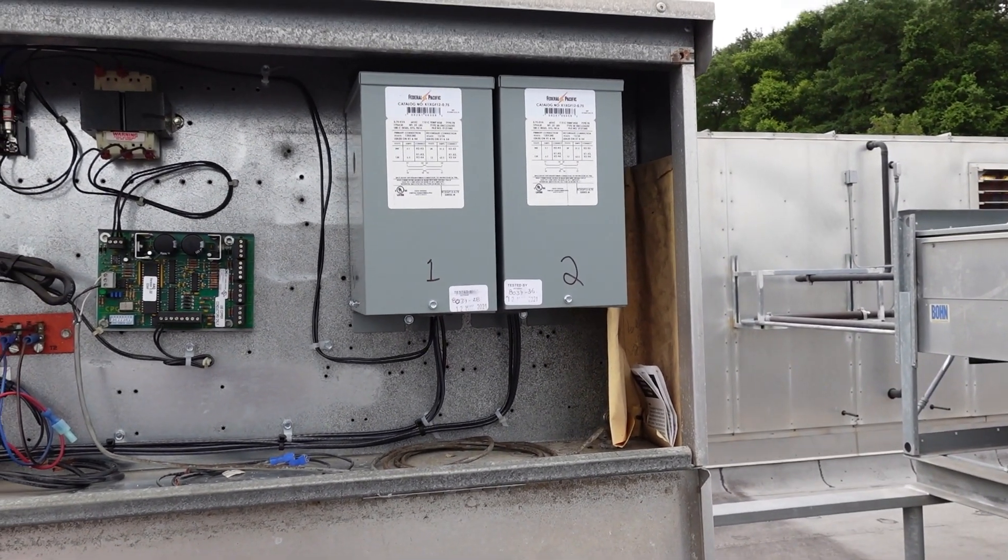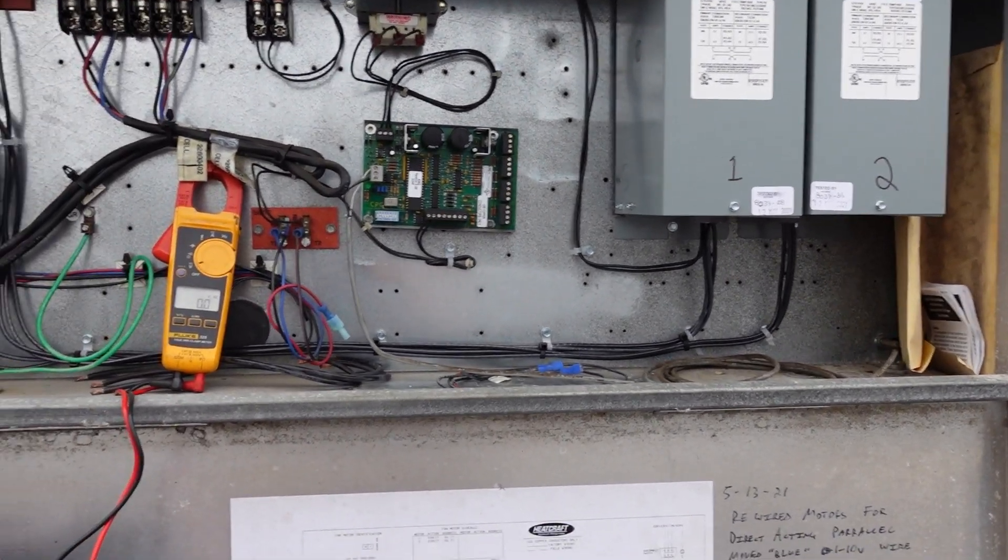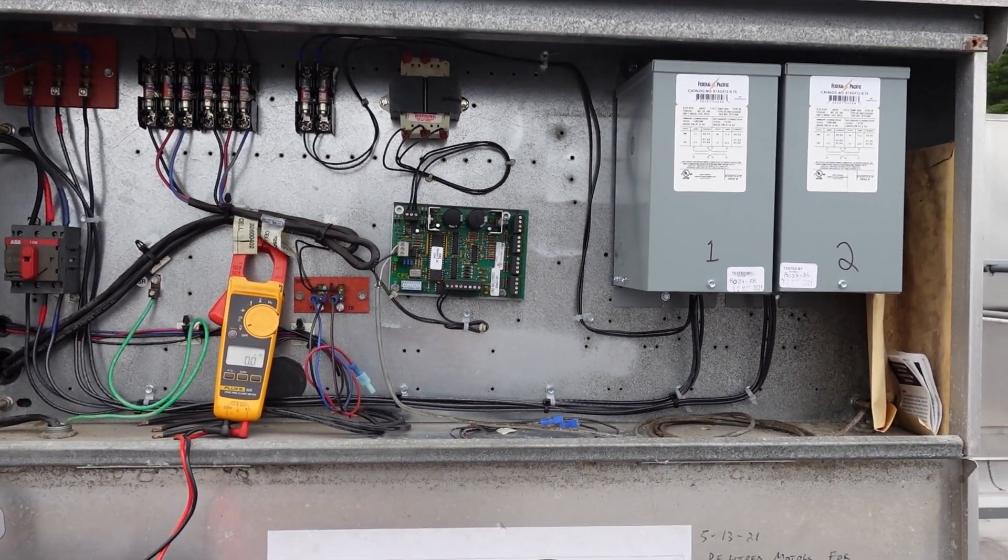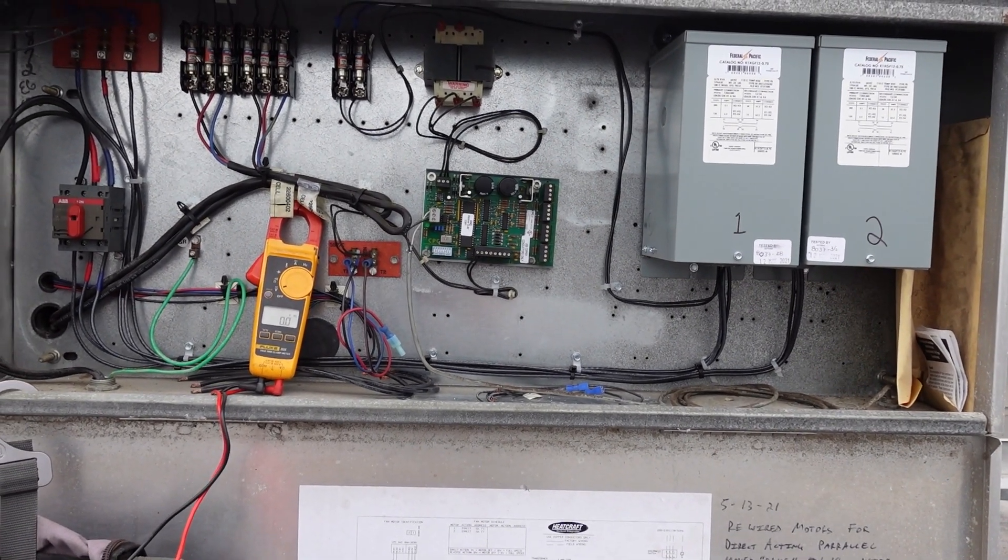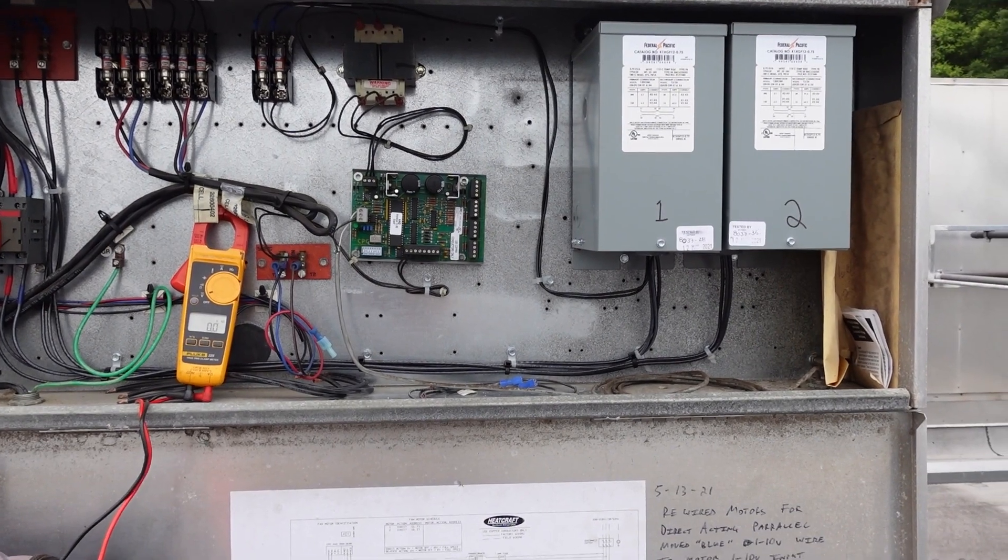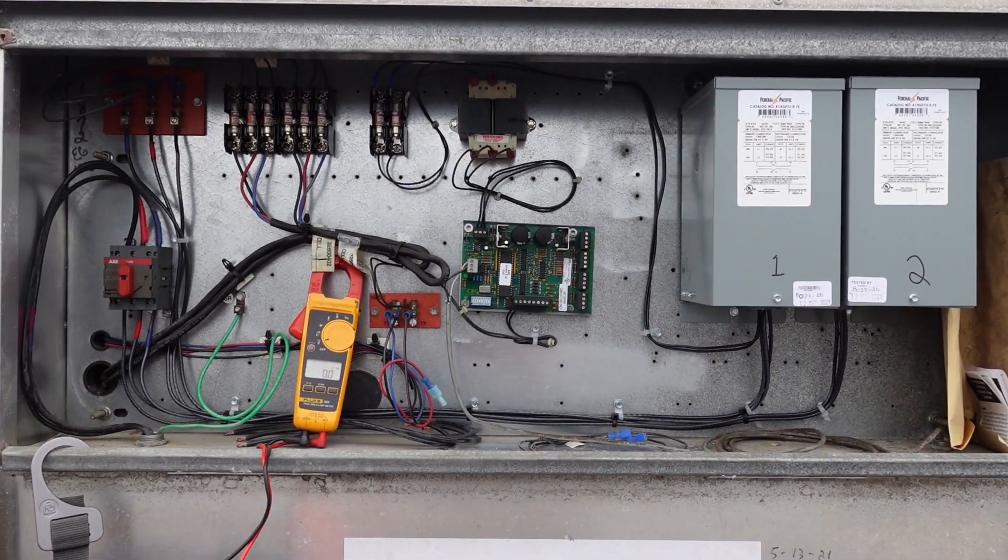We've added buck and boost transformers in the boost configuration because our incoming power supply to these units is, well I shouldn't say super low, it's low and it gets lower in the afternoons, especially on hot days because of the utility company, so we're trying to mitigate motor failure issues.